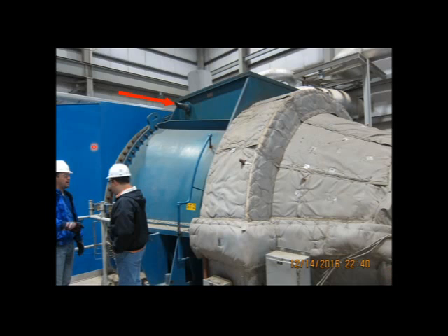So the problem that we found was there. This is the turbine exhaust. Here's the turbine annulus. It goes into this exhaust connection here. And this particular unit again has an axial turbine. There is a bearing that's inside this casing, and there's that bearing.